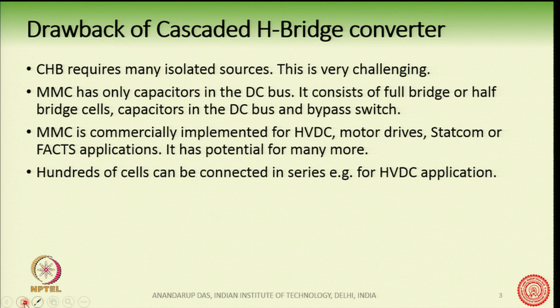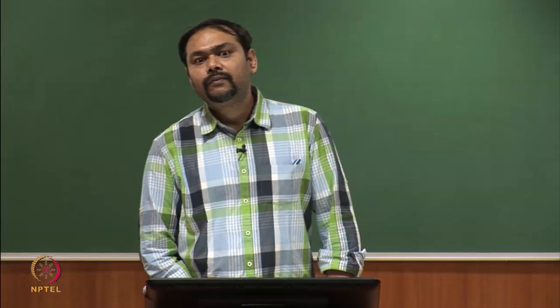MMC does not require any isolated DC source or transformer-fed DC sources. It has only capacitors in the DC bus. At the same time, it retains the advantages of modularity and scalability — many identical low-voltage cells are cascaded to produce very high voltage. The advantages of CHB are retained in MMC, but the requirement for isolated DC sources is removed.